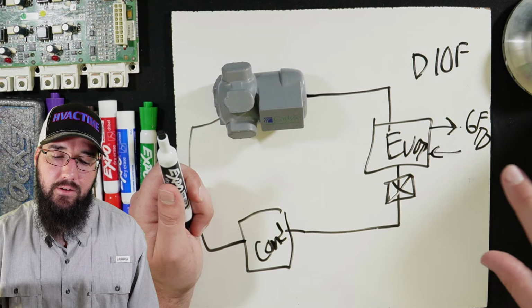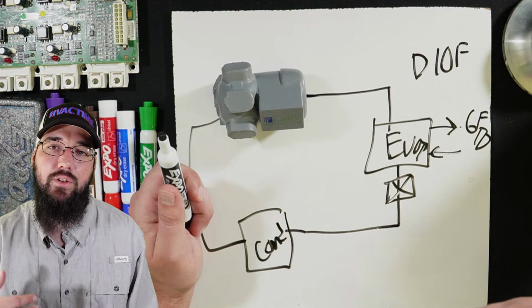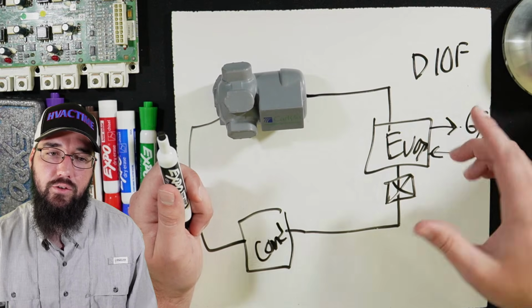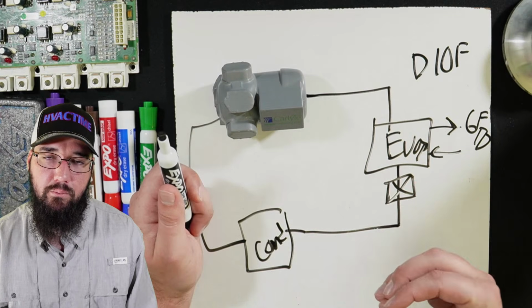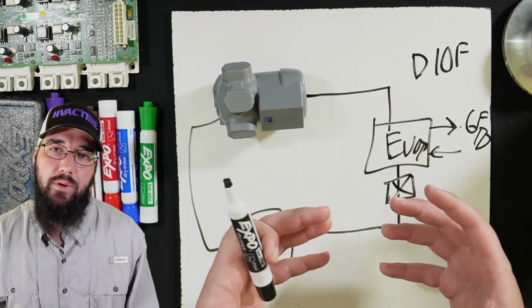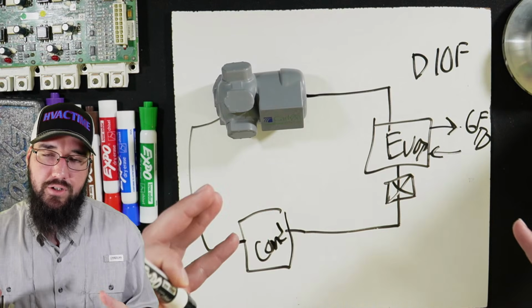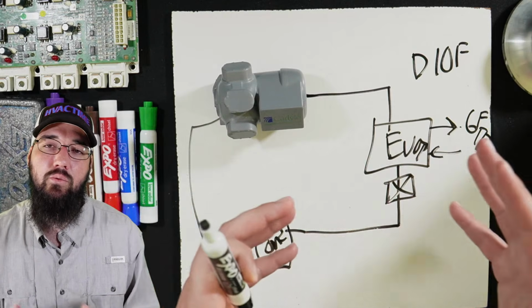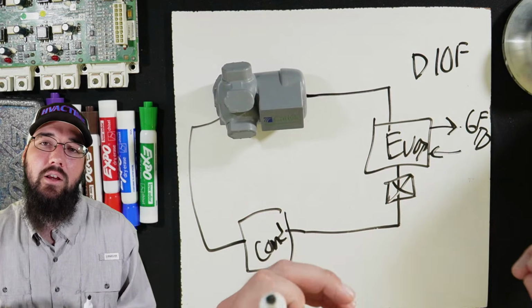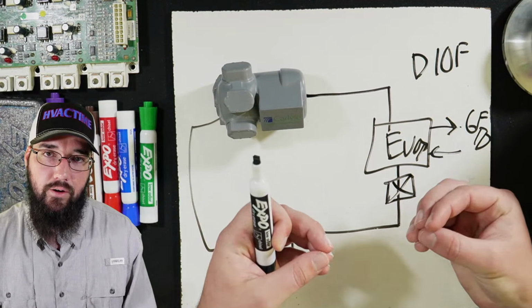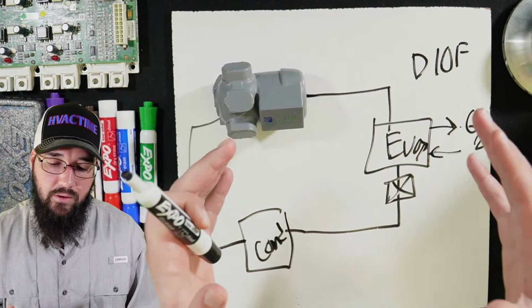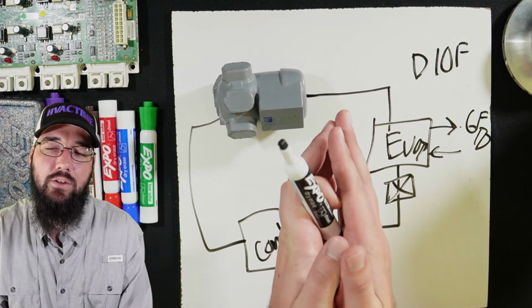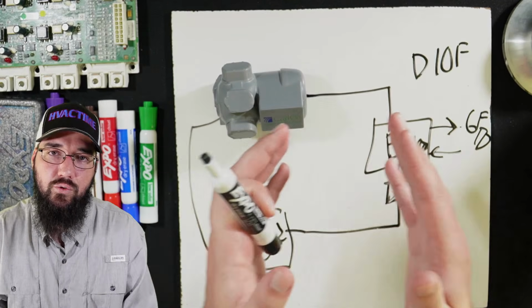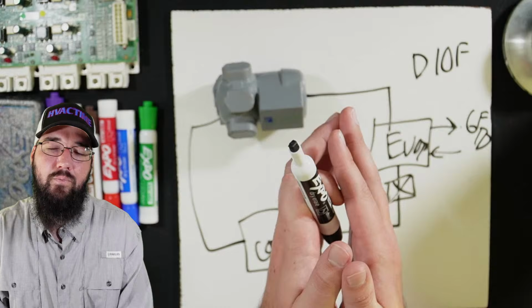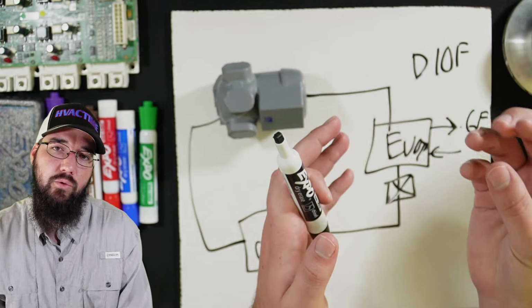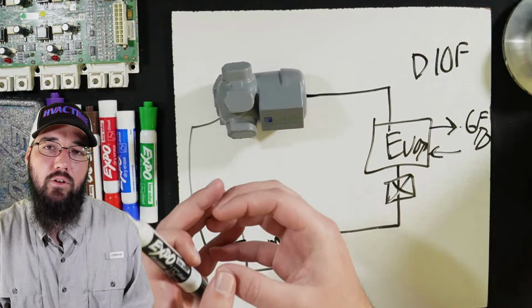But as the evaporator unloads, there's less BTUs going through it. The circuit is having to manage a lower capacity. It also means that we don't need as much difference in temperature between the water and the refrigerant to move the amount of BTUs required. And approach is showing us that we don't need as big of a difference because it is reducing. So the total volume of heat transferred can lower.